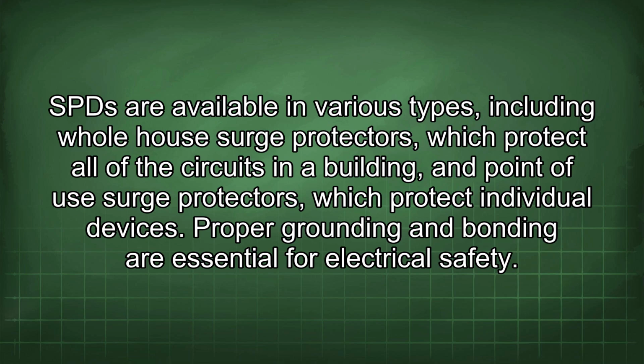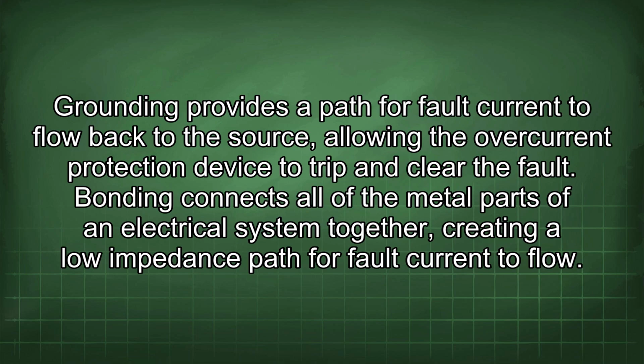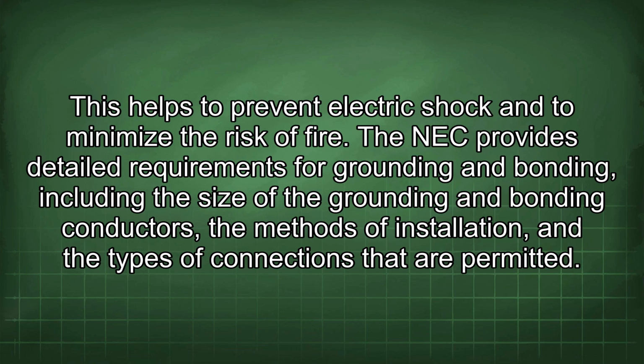Proper grounding and bonding are essential for electrical safety. Grounding provides a path for fault current to flow back to the source, allowing the overcurrent protection device to trip and clear the fault. Bonding connects all of the metal parts of an electrical system together, creating a low impedance path for fault current flow. This helps to prevent electric shock and to minimize the risk of fire. The NEC provides detailed requirements for grounding and bonding, including the size of the grounding and bonding conductors, the methods of installation, and the types of connections that are permitted.